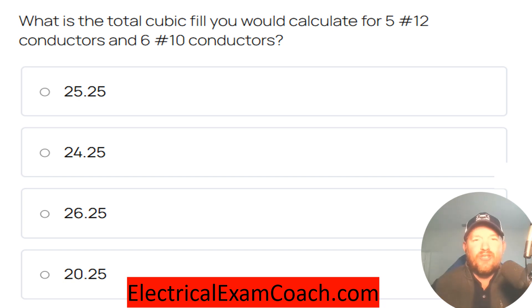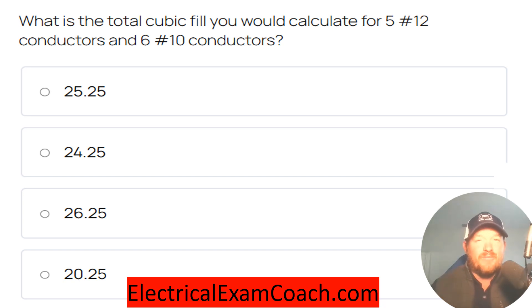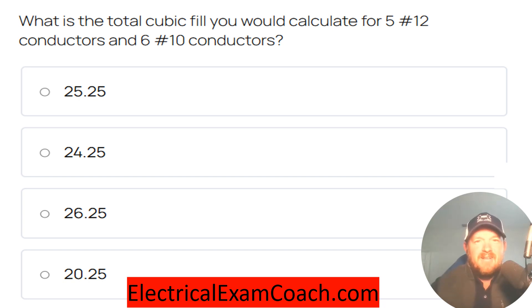What is the total cubic inch volume that you would calculate for 5 number 12 conductors and 6 number 10 conductors? The correct answer is 26.25.